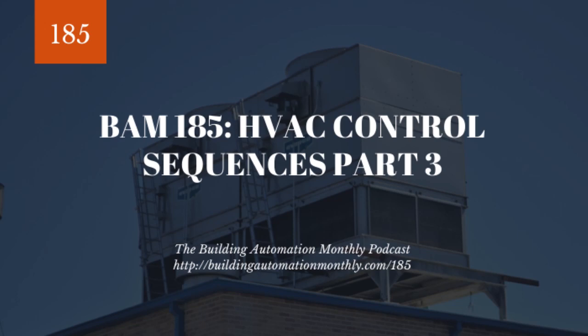But when we're dealing with a single path constant air volume unit, we are typically, as I mentioned, varying our discharge air based on space reset. And so we typically will have some form of reheat as well. And that reheat will typically be used both for dehumidification sequences as well as just for controlling discharge air.